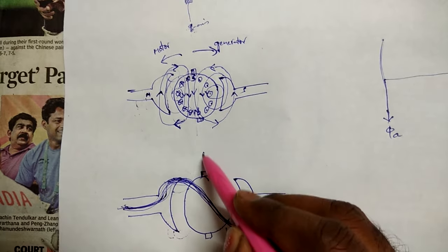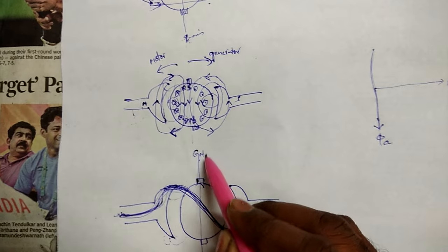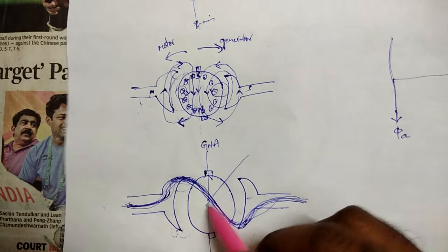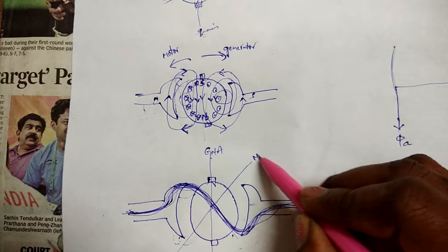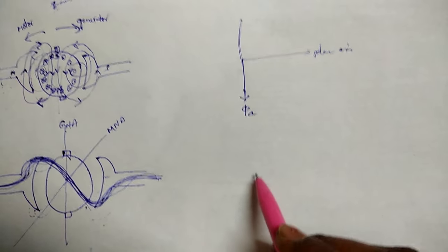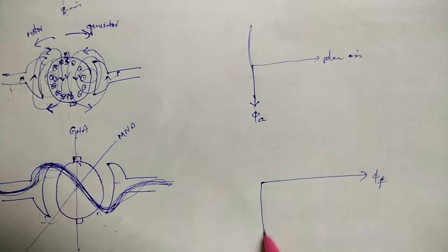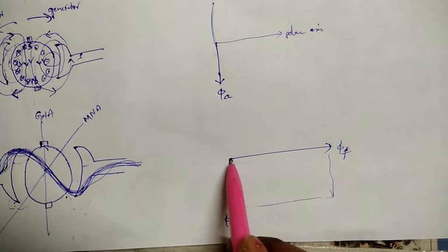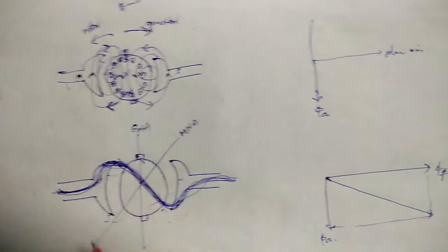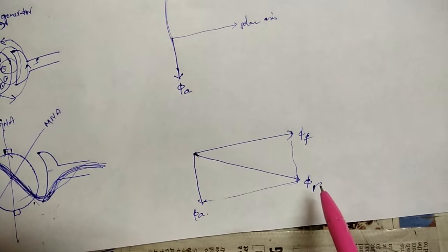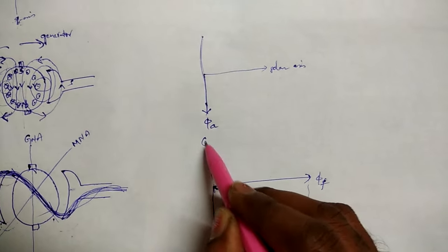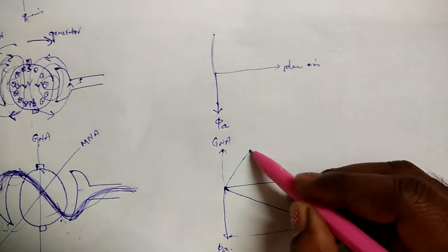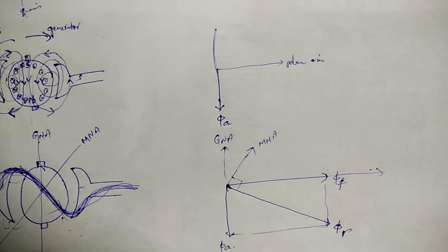GNA is along the brush axis and is always perpendicular to the polar axis. But MNA is always perpendicular to the resultant flux. Since the resultant flux is now distorted, MNA is perpendicular to this resultant flux and is shifted from the GNA. In the phasor diagram, phi-F is in one direction, phi-A is perpendicular to it, and the resultant phi-R is the vector sum of the two. GNA remains perpendicular to the polar axis, while MNA is now perpendicular to phi-R.